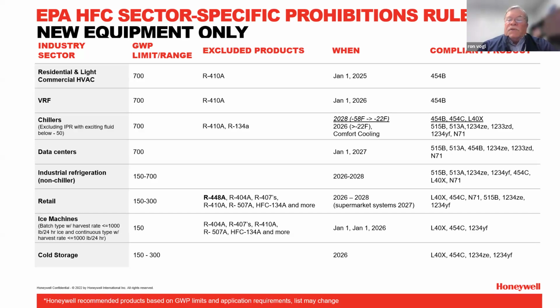We've reached the limit of developing high capacity, medium pressure refrigerants that are A1, ASHRAE rated, non-flammable. And the reason for that is that the flame suppressant that we use in a lot of these refrigerants is 125, and it has a high GWP. So 32 is mildly flammable, for example. In the case of 410A, how do you make it non-flammable? You add 50% 125, and now you've got an A1 blend.